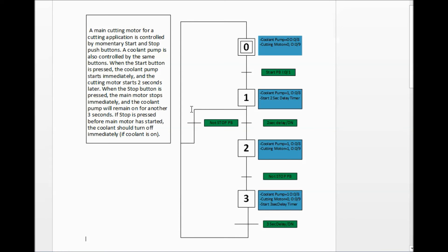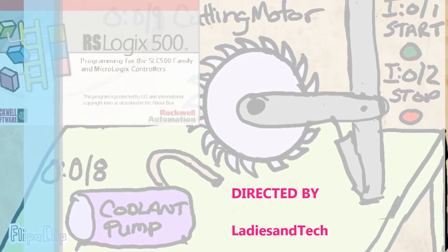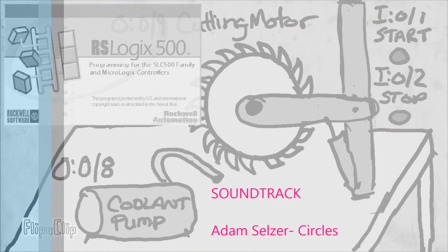To handle that case, we need an OR situation — two possible paths from step 1. We can continue from step 1 to step 2, or take an alternative route straight back to step 0. So once we're at step 1 with the coolant pump on but the motor not yet started, if the operator presses stop, we head straight back to step 0 which shuts off the coolant pump. Otherwise we wait for the two-second delay and continue the normal process. That's our completed sequential function chart — a good map for writing the program. Now let's get to RSLogix 500 and put this into ladder logic. Subscribe so you don't miss the next video!